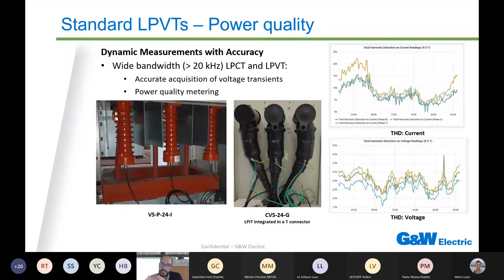Regarding high frequency, normally we have a bandwidth above 20 kilohertz, both for low power current transformers and low power voltage transformers. So our sensors are used for power quality metering. For example, we used this in a project in Dubai to measure the total harmonic distortion present on the network. This was because the distributor wanted to investigate the harmonic content generated by the solar farm.